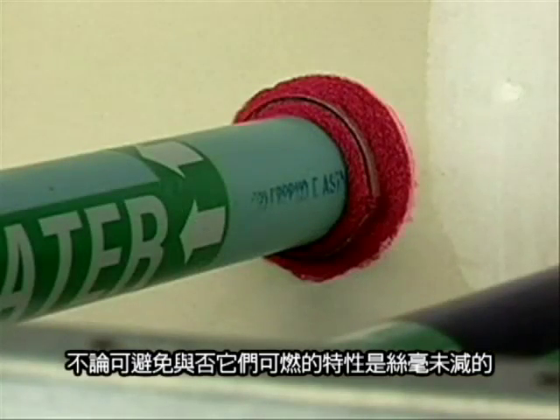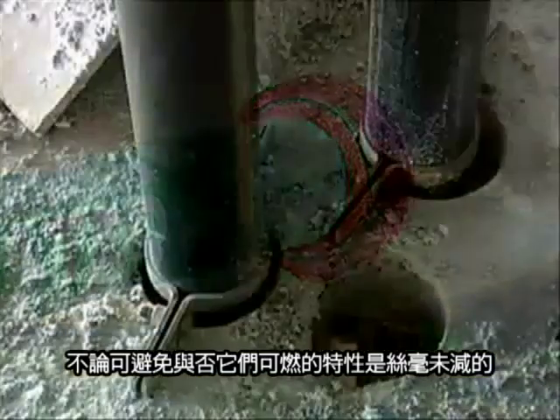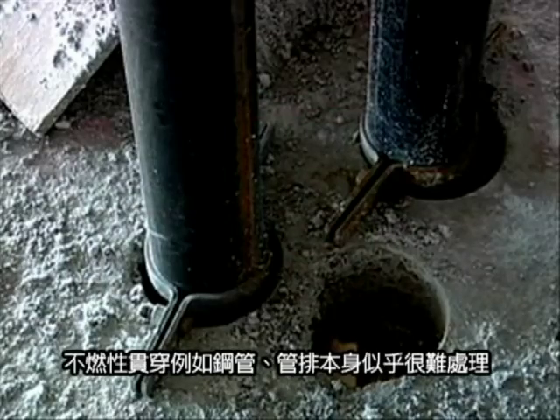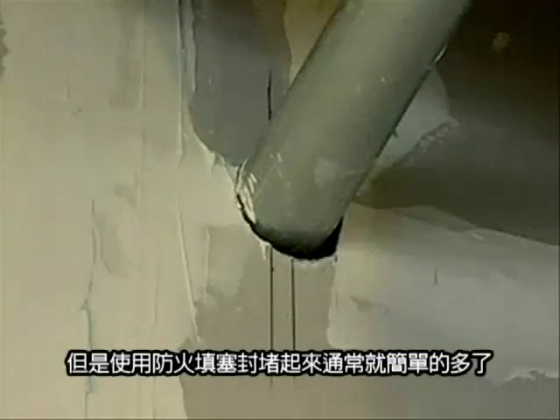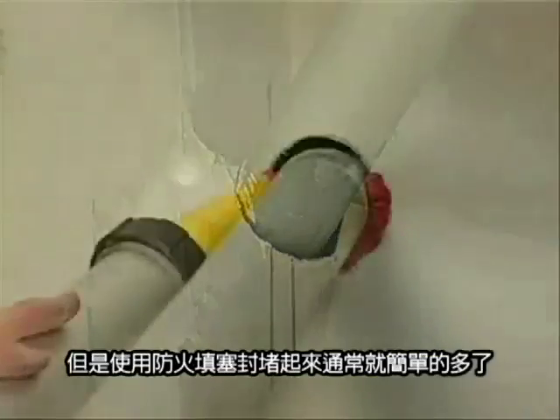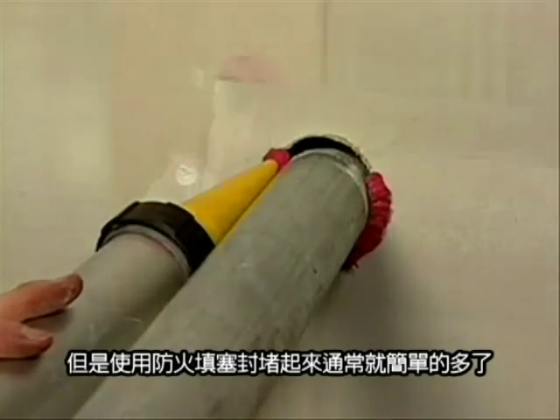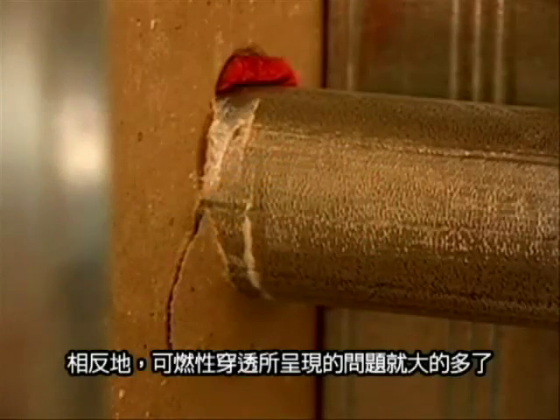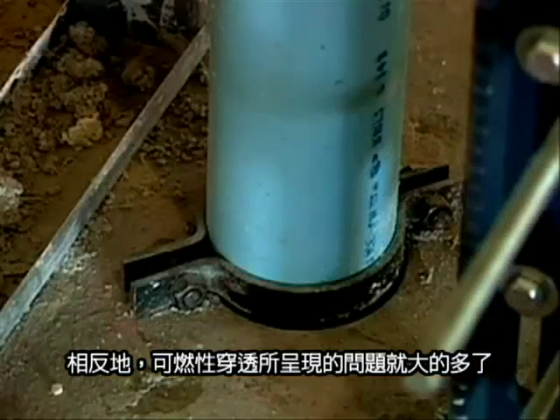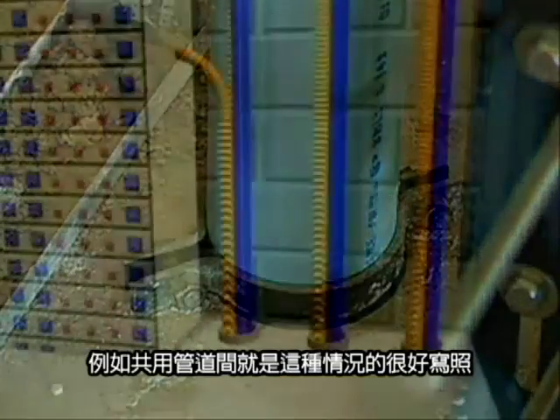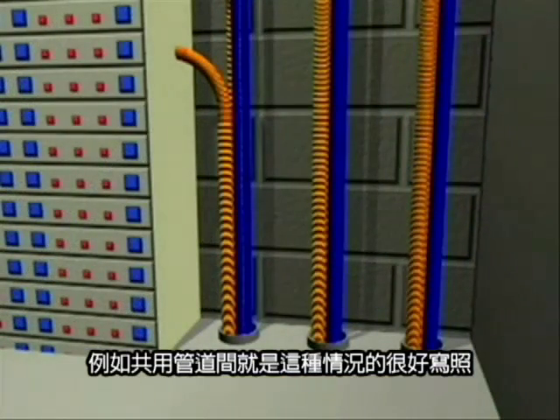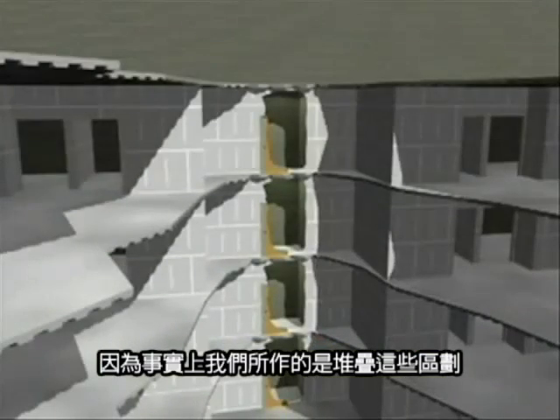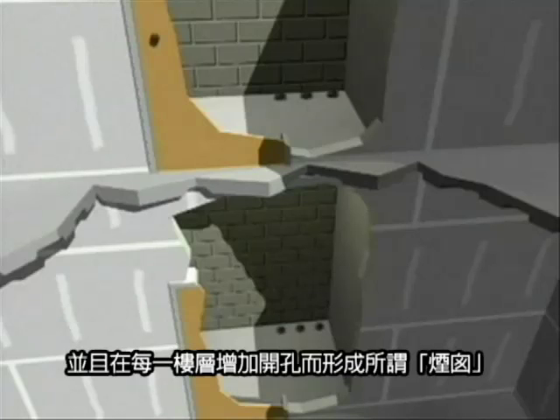Unavoidable or not, however, they are no less combustible. Non-combustible penetrations like steel pipe and conduit are difficult enough themselves to deal with, but can usually be handled simply with fire stop sealant. Conversely, combustible penetrations present a much greater problem. Utility closets illustrate the point well because, in effect, what we are doing is stacking these compartments and adding openings in each floor, creating a chimney.